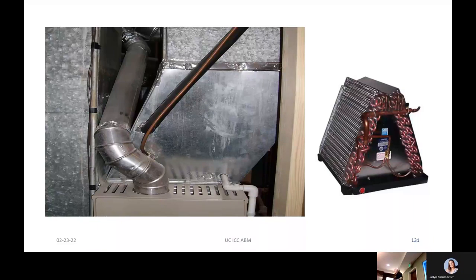I wanted you to see this picture. This is what your air conditioning coil looks like inside your furnace. You can see by the tight design if you don't use the right coil we're going to have a lot of pressure drop going through it. What's wrong with this picture? It's laying right on that side of the coil. Air comes up through the bottom and goes both ways on that A coil. No air goes through the left side of that coil. That simply will not function. I caught it before they turned it on, but it doesn't work. This is an HVAC guy.